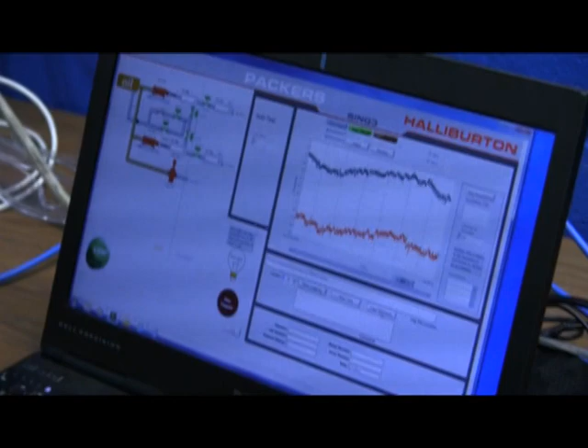Okay, are we going to test just one line, or both of them? We can do either, but we'll see the pressure build up on both since we still have our jumper in place. They're connected in the back, so we'll see the pressure rise on both lines, so Halliburton will know both lines are jumpered together and both sensors will see the pressure go up and hold.